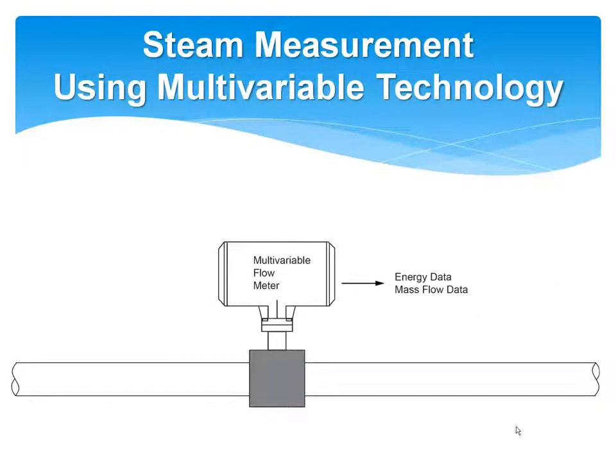Some of the newer technology meters are actually multivariable meters, which have integral velocity, pressure, and temperature measurements inside, and will calculate the mass flow and energy data inside the meter head itself. This gives a couple of benefits. Number one, you can calibrate the meter with all the sensors intact, which results in some improvement in accuracy. Also, you can greatly reduce the overall installed cost of the metering system. So again, that's something to be aware of as we run through this.